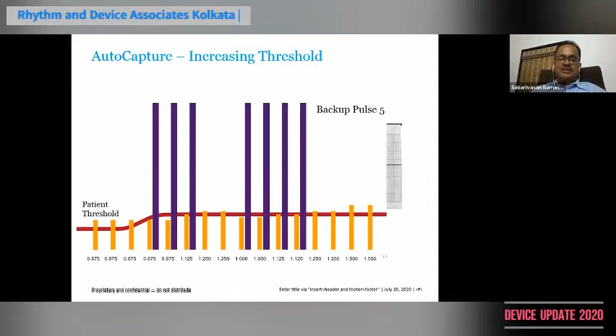So this is the primary objective, but it also gives secondary benefits to the patient. With a smaller battery, you can do the same thing because your safety margins are going to be less, and your longevity can be longer. That is the biggest advantage of this algorithm. It makes sure that 100% the patient is always taken care of. There is no loss of capture. At the same time, it is also reducing the battery size. It is also not compromising on the longevity of the devices.